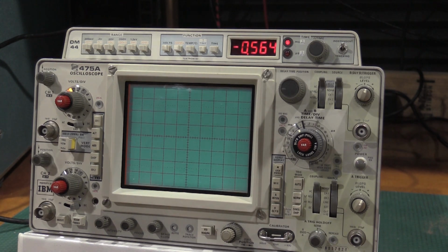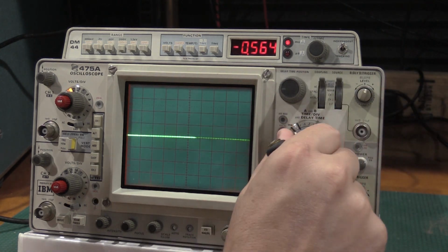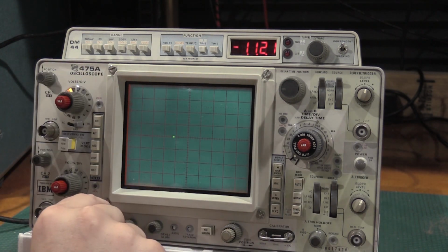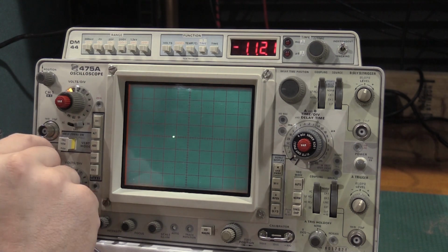So that looks good. I don't need to do this with the calibrator, but if I hit the beam finder, we get a compressed waveform. So everything looks good there. Okay, so now we're going to deviate a little bit from the calibration document, but not too terribly, because I want to double check some things before we really get started messing with the geometry and the y-axis alignment. So I want to come down to XY mode, and we'll bring the intensity down a little bit because I don't like that spot shape actually. So the spot's kind of oblong and strange. So I want to do some astigmatism adjustments. Ooh, that looks a lot better.